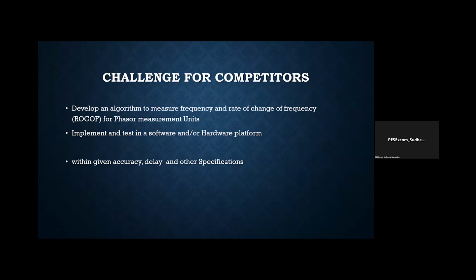If you followed Dr. Anton's presentation, he mentioned there are many measurements taken from the PMU: phase is one, frequency is another, and then there's rate of change of frequency. Dr. Anton also said the measurements of the PMU depend very much on the frequency, and there's an issue with the error in this measurement. So tracking this frequency correctly, and also the rate of change of frequency, is very important in a rapidly changing environment.